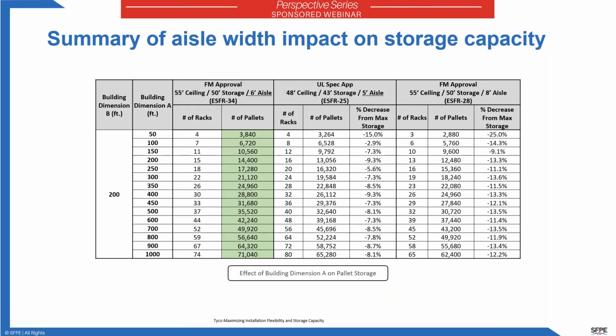And this last table just provides a summary. As I noted, my example focused on a building warehouse area that was based on a 200-foot dimension along the width of the rack. I did a 200 by 200 example of a 40,000 square foot area, which is this line here. The scheme that again has the potential for the highest number of pallets that could be stored is the 55-foot ceiling approval with the ESFR 34 and 6-foot aisles.